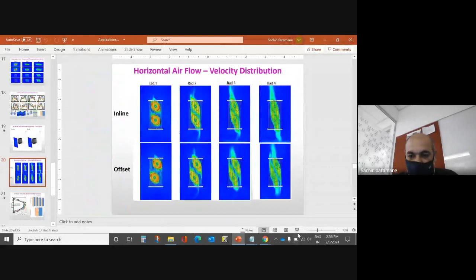Again, here you can see the flow and temperature distribution. This is the velocity distribution when the fans are inline and offset, when they are mounted on the side. So you can see with an increase in the offset, there is an increase in the area used for heat dissipation, which gets utilized significantly compared to when the fans are placed inline.